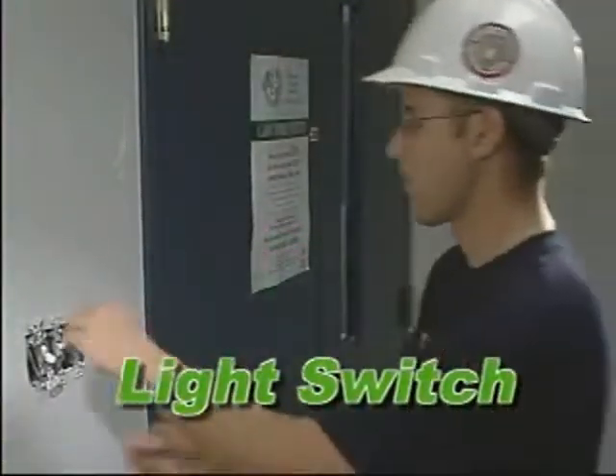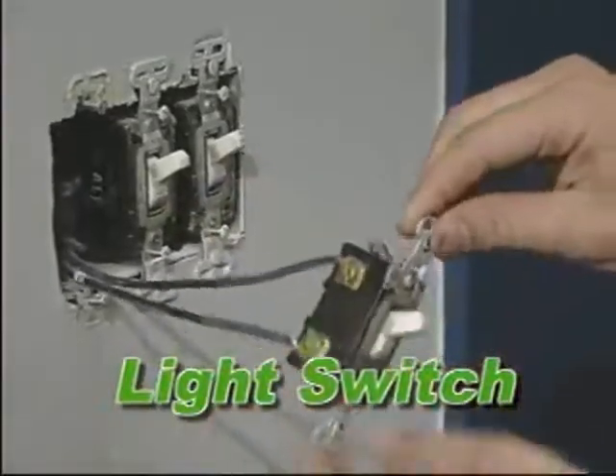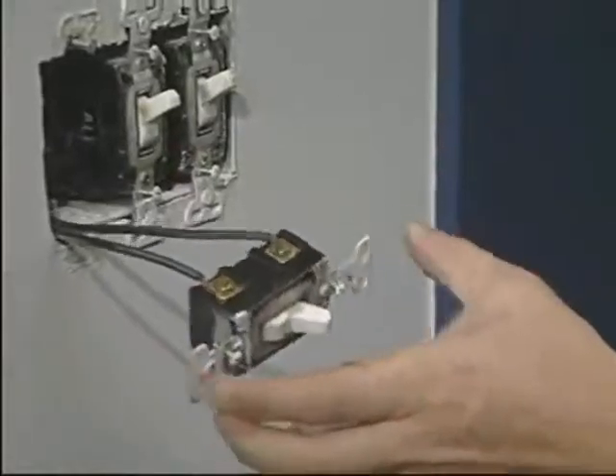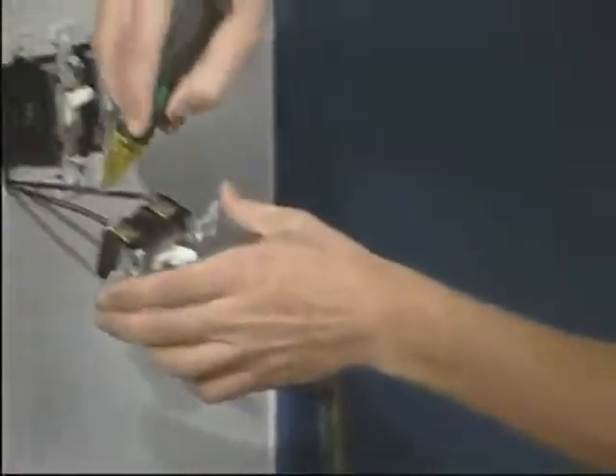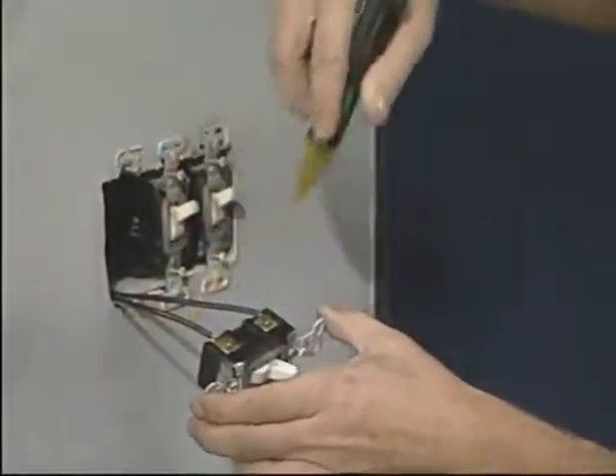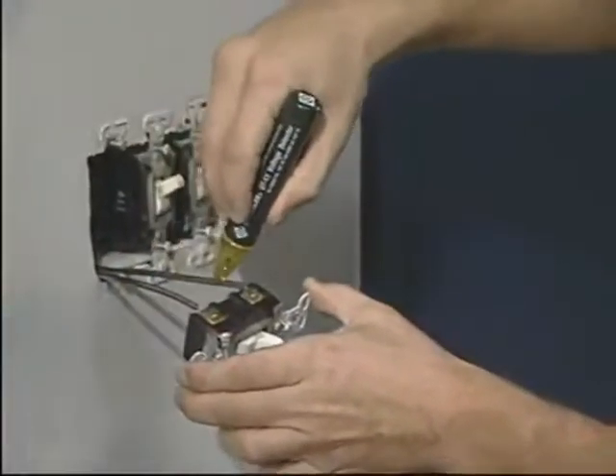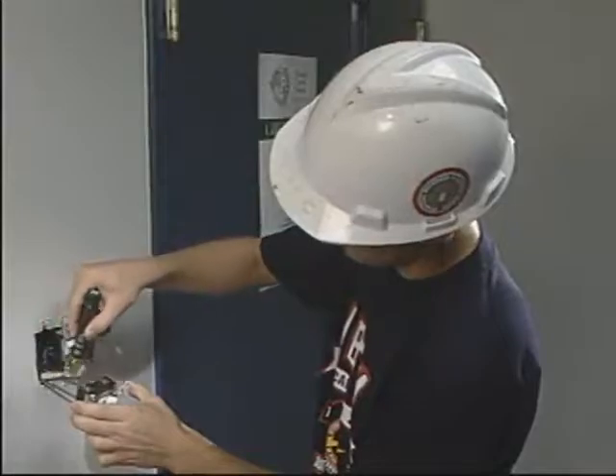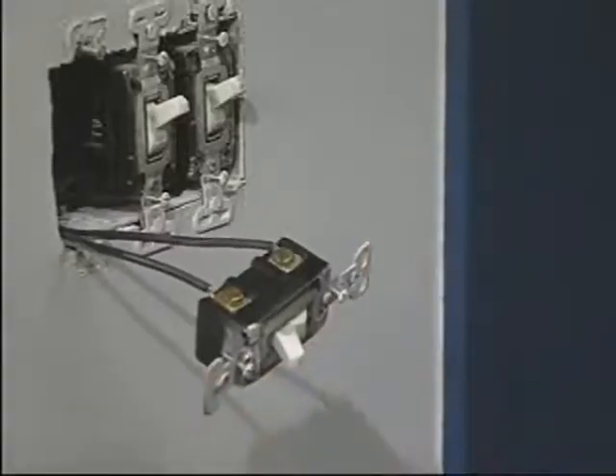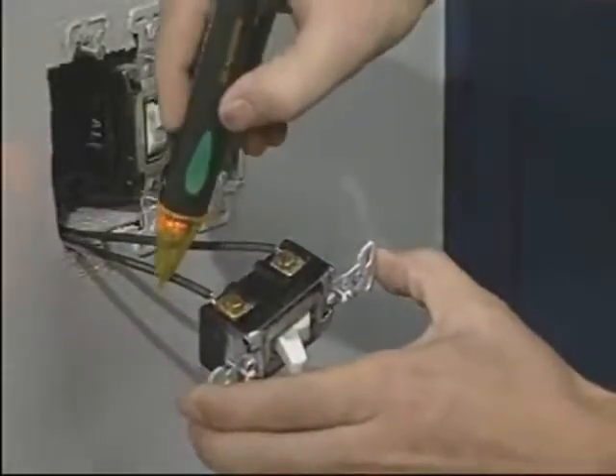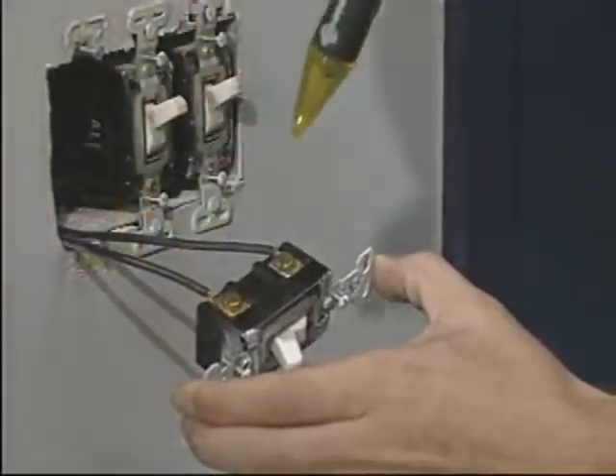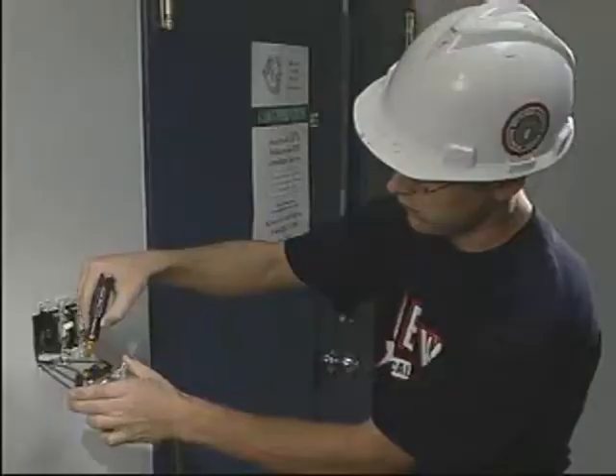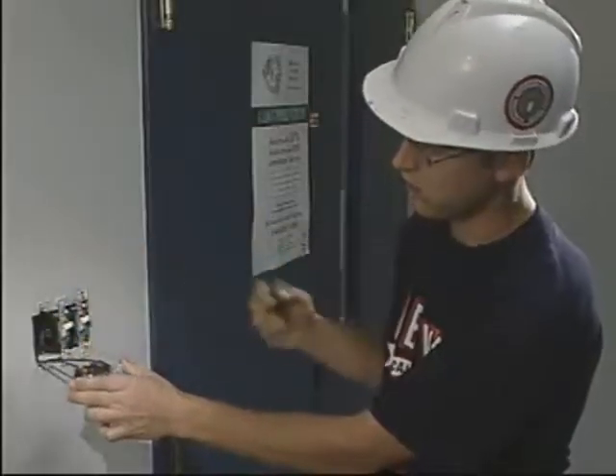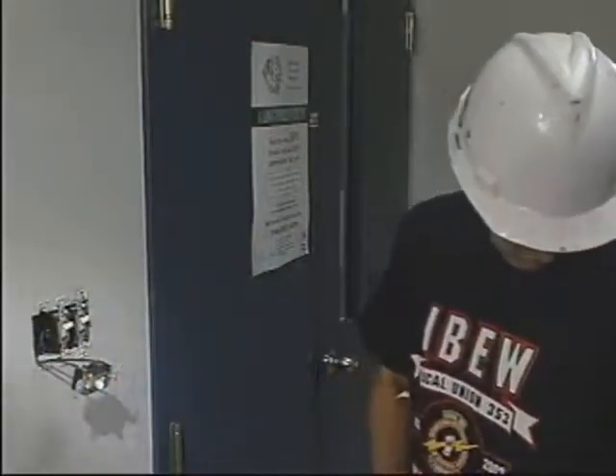To test a light switch, make sure the light switch is in the off position. Place the flat part of the GT11 probe tip against the incoming wire. There should be an audible and visual alarm. Do the same for the outgoing wire. There should be no alarm indication. Turn the light switch on. Test both wires again. We find they both cause an audible and visual alarm. The switch is working and both wires are hot.